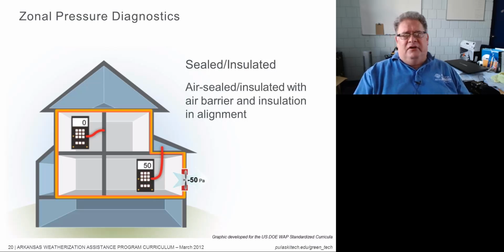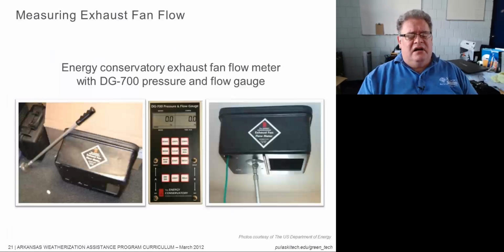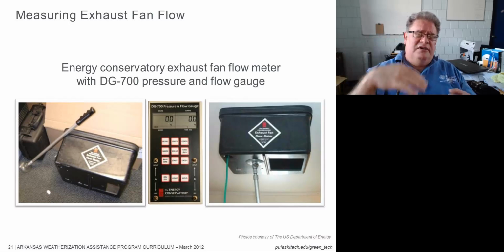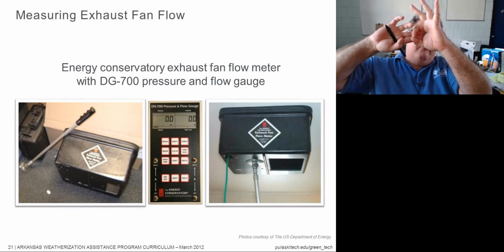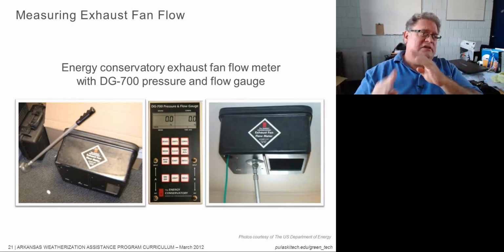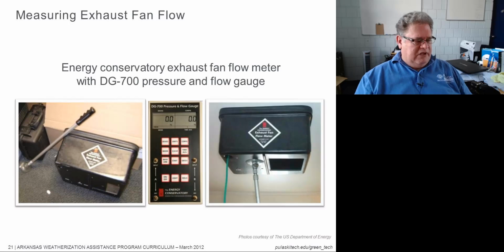So exhaust fan flow. This is something new that ASHRAE standards that DOE have adopted are causing us to do. We need to have something that looks very much like a pressure pan, except it has a big hole in it. It has a calibrated hole right here, and that hole has a shutter or a slide in it. So you've got a hole, and we can start closing off parts of that hole. We've got 3 positions, I think, on it. You can connect it to a manometer. And then on the other side of it, which is not shown in these pictures, there's a chart.